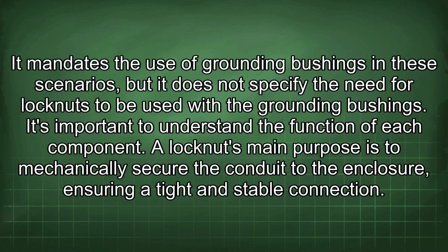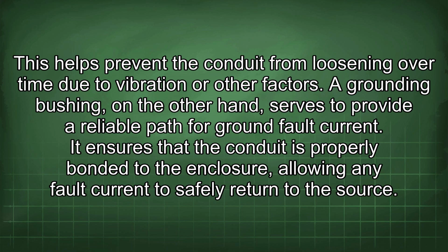It's important to understand the function of each component. A locknut's main purpose is to mechanically secure the conduit to the enclosure, ensuring a tight and stable connection. This helps prevent the conduit from loosening over time due to vibration or other factors. A grounding bushing, on the other hand, serves to provide a reliable path for ground fault current. It ensures that the conduit is properly bonded to the enclosure, allowing any fault current to safely return to the source.